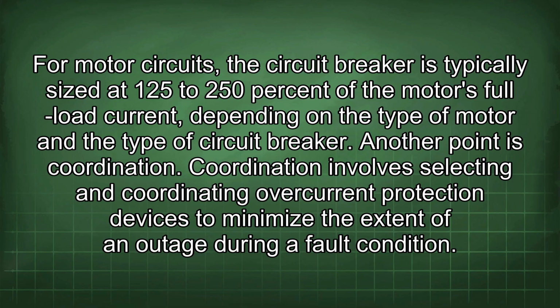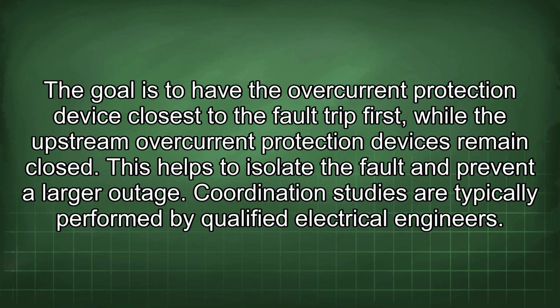Another point is coordination. Coordination involves selecting and coordinating overcurrent protection devices to minimize the extent of an outage during a fault condition. The goal is to have the overcurrent protection device closest to the fault trip first, while the upstream overcurrent protection devices remain closed. This helps to isolate the fault and prevent a larger outage. Coordination studies are typically performed by qualified electrical engineers.